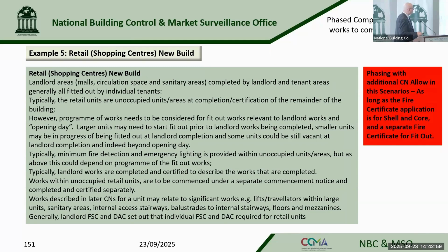And then similarly, retail shopping centre, similar situation. The landlord areas, the mall circulations might be fitted out, might have an anchor tenant who might fit out their unit as well at the commencement of the work. So you might have areas of the anchor tenant and the common areas might be finished, and you will have areas around that which will be unfinished. They will still be included in the fire cert, but they will be demonstrated to have the minimum requirement for fire separation and fire detection.